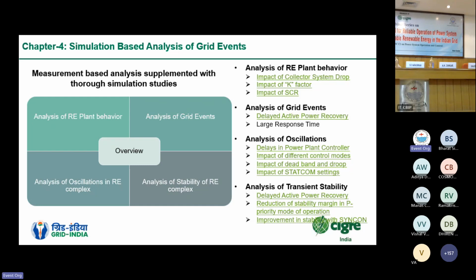We have recently commissioned StatComs in the RE pocket, and one of the conclusions of the study was that StatCom settings also need to be tuned appropriately so that they provide the desired behavior rather than amplifying or magnifying the oscillations. One of the important aspects and threats in the RE pockets is the issue of transient stability. It is very important that the complete RE pocket remains stable during a fault event. We should be very much aware that such transient stability issues can cause a major tripping, where we can lose a large chunk of generation, and a complete system can get desynchronized from the rest of the system.